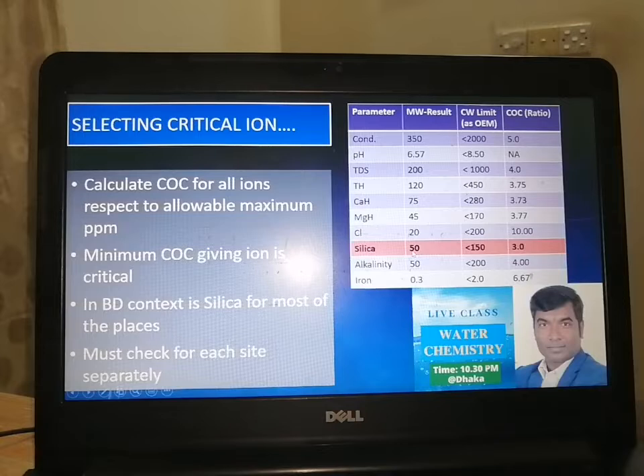For any system, considering it is a chiller or a cooling system, the OEM guidelines show the limits I have to maintain: conductivity should be less than 2000, pH should be less than 8.5, TDS 1000, total hardness less than 450, calcium hardness less than 280, magnesium hardness less than 170, chloride less than 200, silica less than 150, alkalinity less than 200, and iron less than 2. So these are the guidelines we have from the OEM. That means the machine manufacturer gives us the guideline.